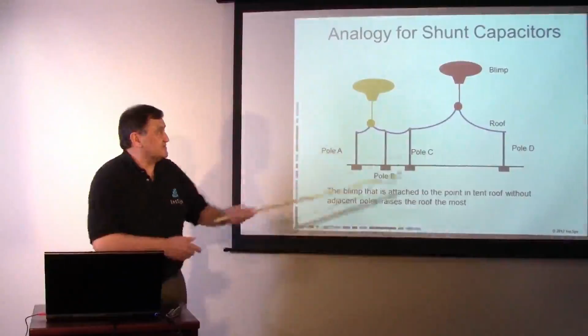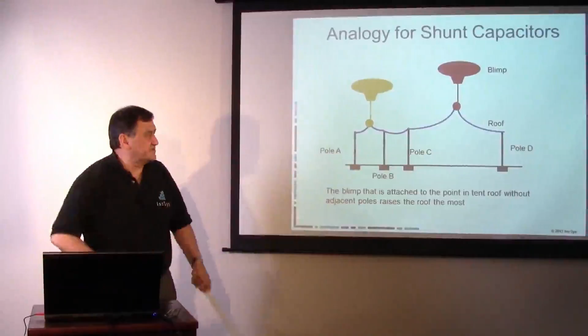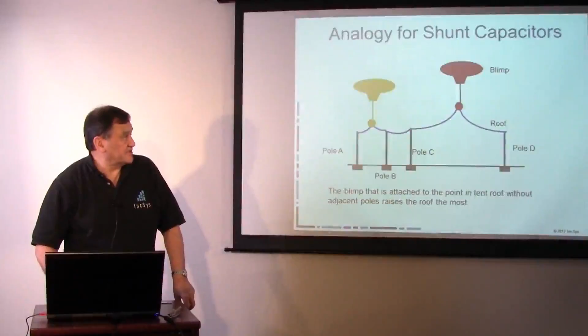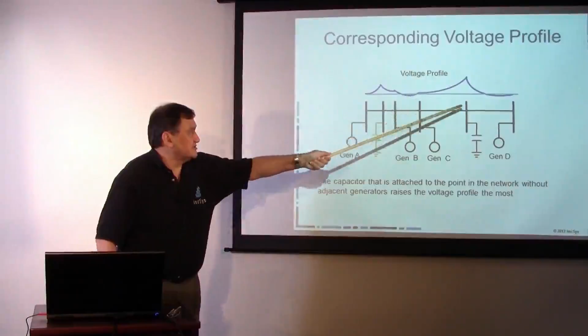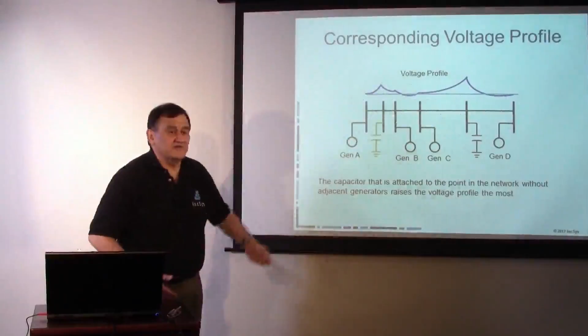That becomes the anchor point. And it's only your generators or your static var controllers which provide those anchor points. Your capacitors can make a big difference, but they don't anchor the voltage. They really just raise the voltage with respect to the other anchor points throughout your system. So we had a case with the blimp, and we moved to a case where we have generator buses. Our generators are anchoring our voltage at all these points close to the nominal value, and then we apply our capacitors, and they raise the voltage throughout the system.